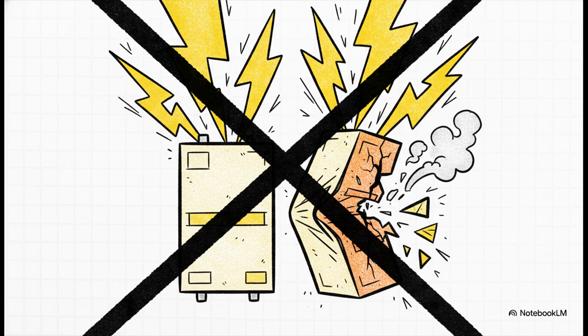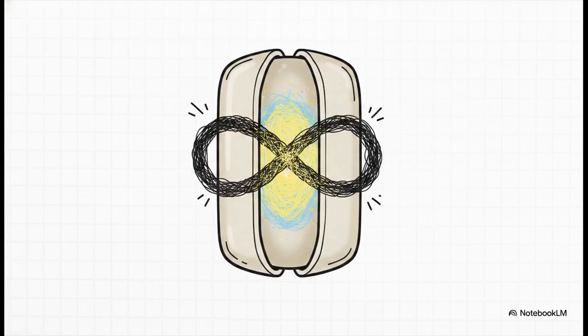Never substitute fuse ratings. If you swap to a 400 amp fuse, you are completely erasing that deliberate protective margin. Put a 400 amp fuse in front of a 400 amp contactor, and you've just broken the entire coordination scheme. During a massive fault, your contactor might warp, melt, or literally tear itself to pieces before that oversized fuse even thinks about interrupting the current. The coordination is precise for a reason. Don't mess with it.